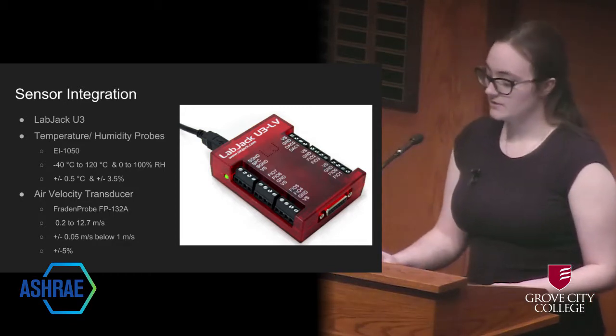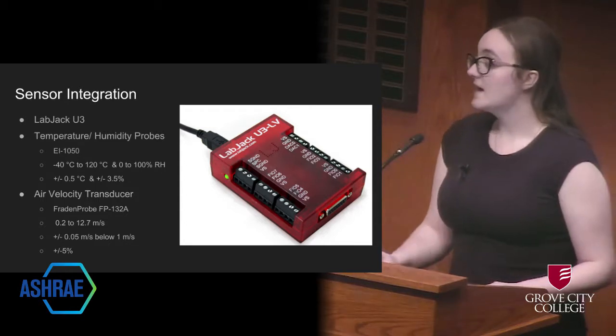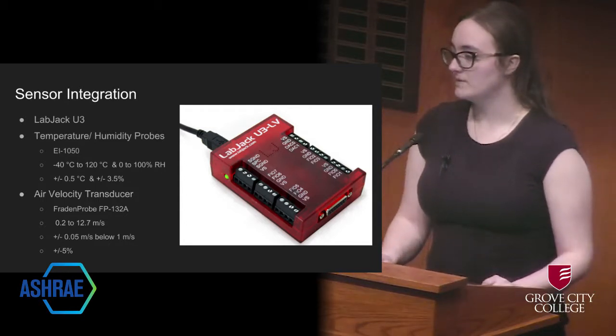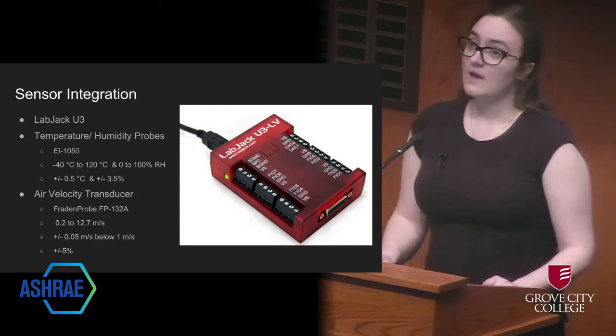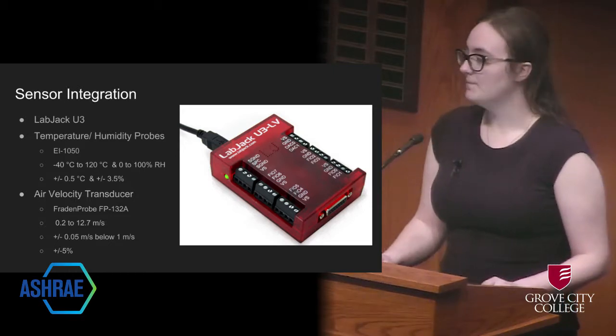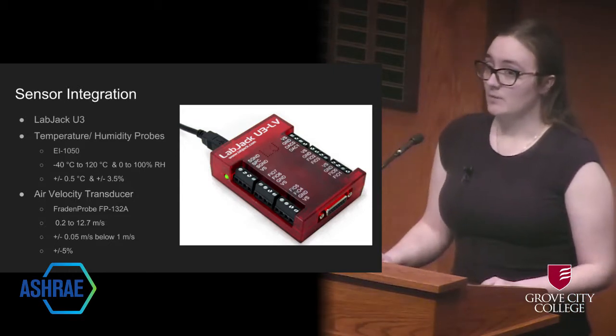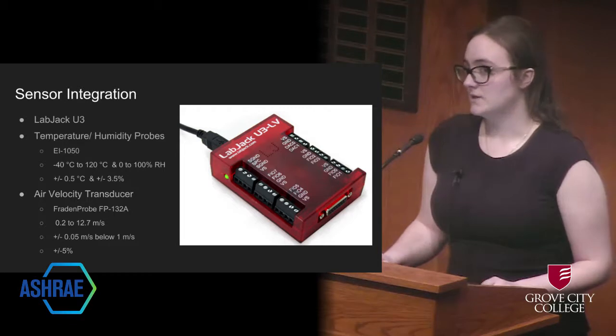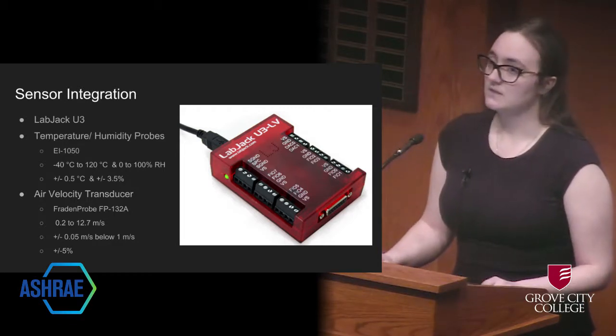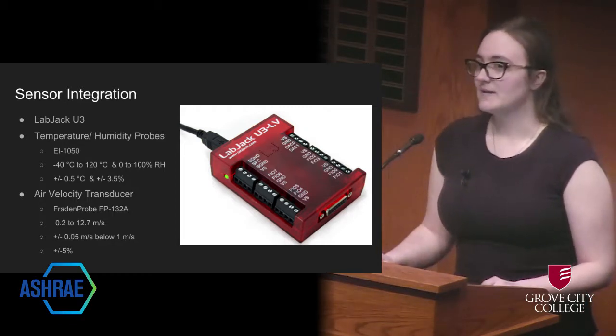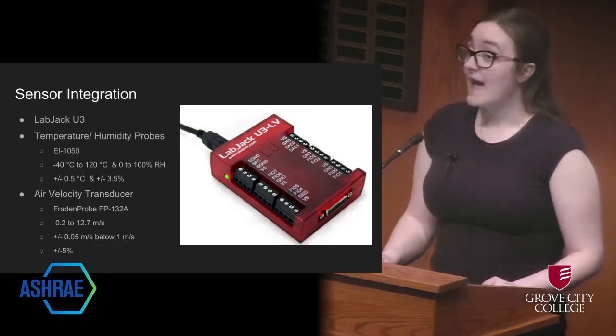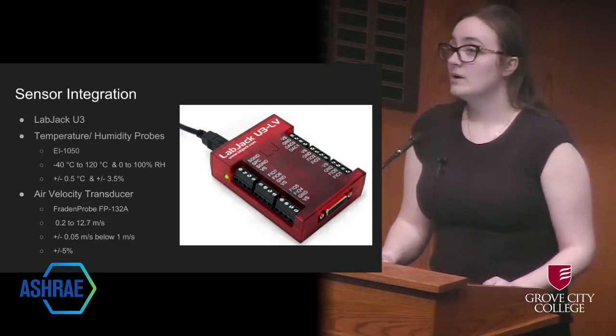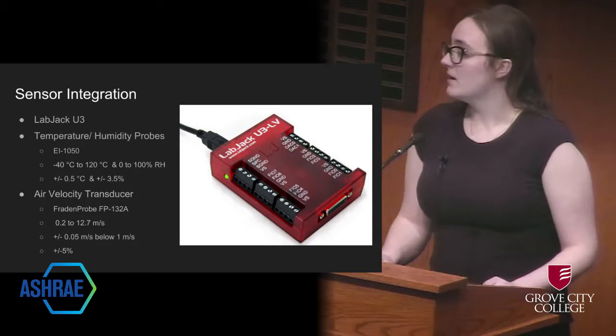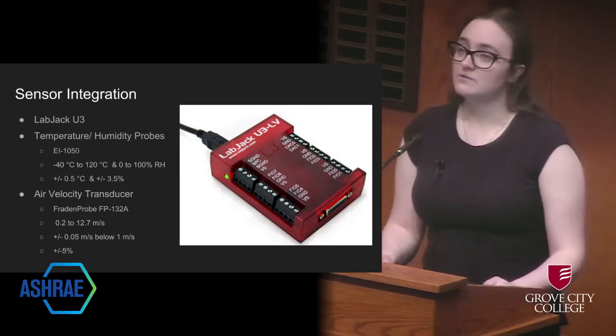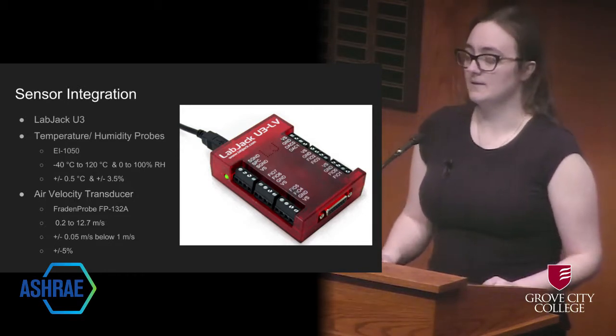The first additional sensors we obtained were the EI1050 temperature-humidity probes, to measure temperature and humidity before and after the coil. The operating range for these probes was between -40 and 120 degrees Celsius, and from 0 to 100% relative humidity. The accuracy of these probes was 0.5 degrees Celsius and plus or minus 3.5% relative humidity.